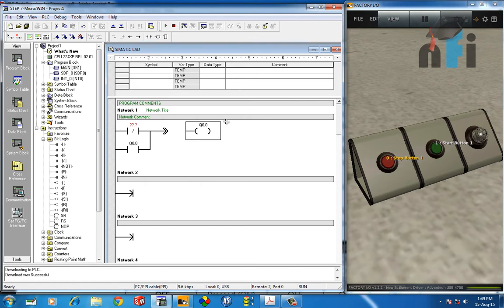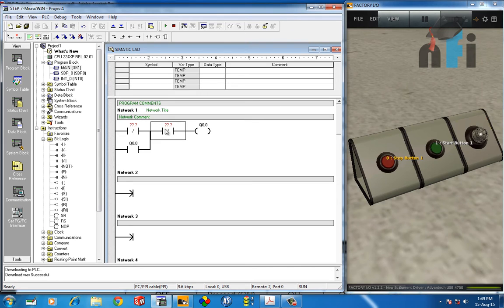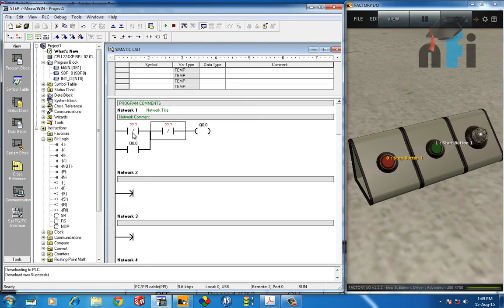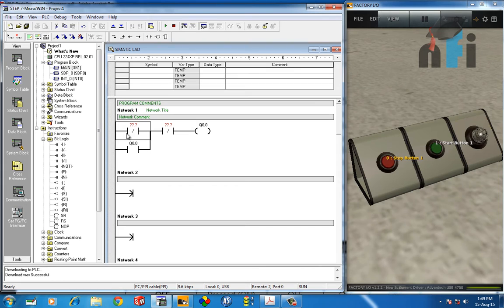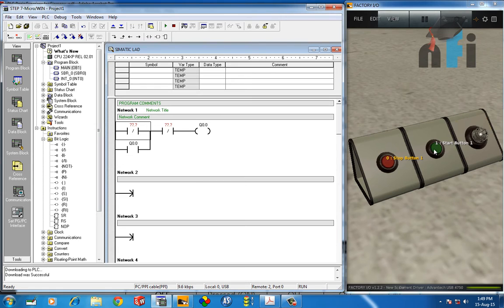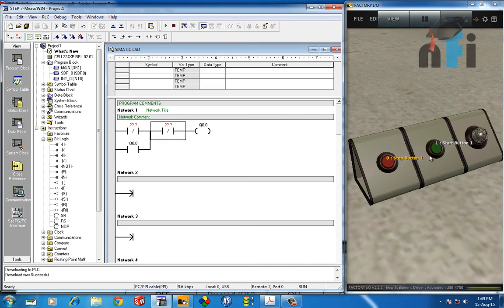To stop something with NO push button, we take its NC. You can see it as a rule or just memorize it: if you want to actuate something using NC, take its NC. If you want to turn on something using NC, take its NC. If you want to turn off something using NC, take its NO, as we did in the last exercise. That's opposite for NO: if you want to turn off something using NO button, take its NC in the PLC. If you want to turn on something using NO button, take its NO.